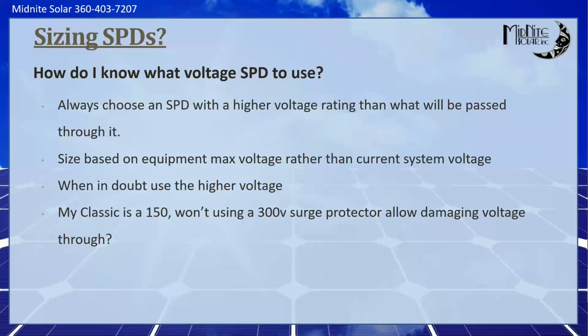The problem with that is that if somebody comes in and expands on that in the future, or the array gets changed in the future, they may miss the fact that that SPD is a 150 and not a 300. So let's say you've got a Classic 200 in there because that's what you had in the truck, or a Classic 250 even is a better example. That's what you had in the truck. You put two 72 cell modules in series and you did 6 strings.